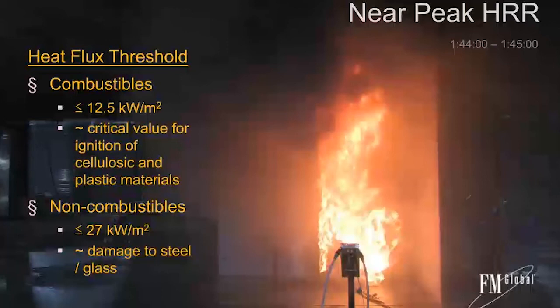And so if you have a combustible object, protection documents such as FM Global's datasheet 1-20 or NFPA's 80A use a value of 12.5 kilowatts per meter squared, meaning that if that much heat is pushed at a combustible object, you can expect it to be involved in the fire. And that's basically a nominal critical value for the ignition of paper or plastic products. And so that's important if you think about how far should an aisle space be between energy storage systems, or what if you have a large trash can, particularly a large plastic trash can, how far away should that be to make sure that fire isn't going to jump to additional combustibles and then spread.